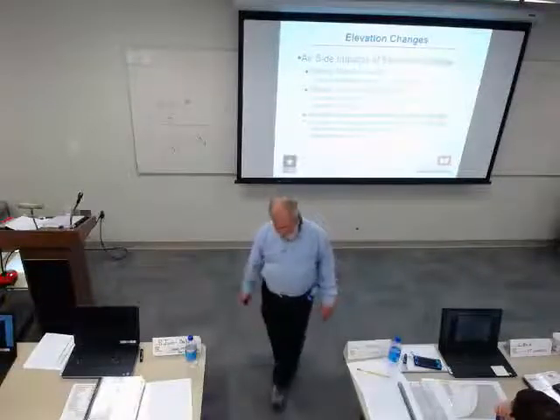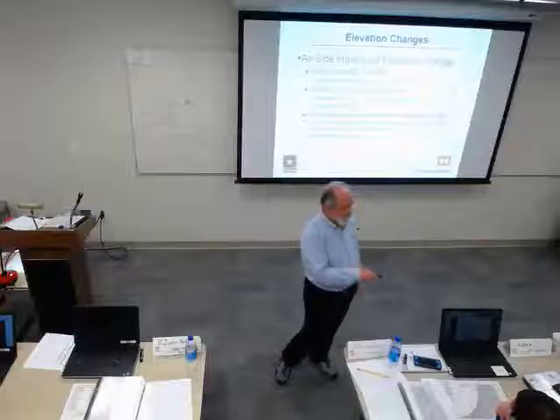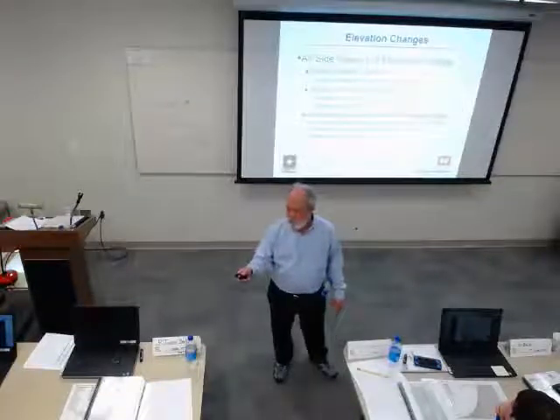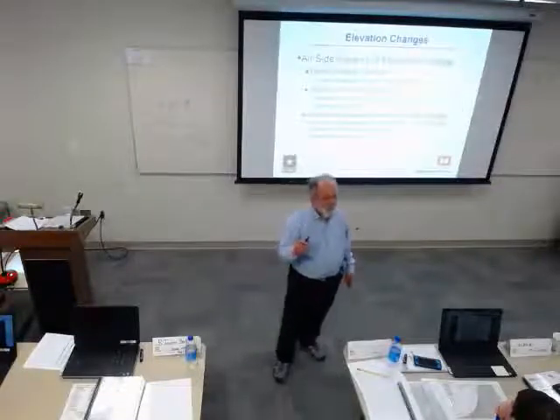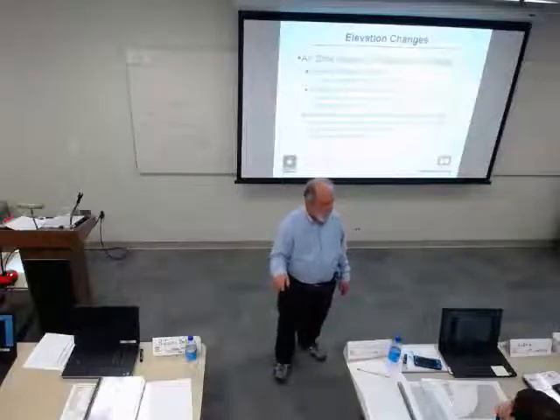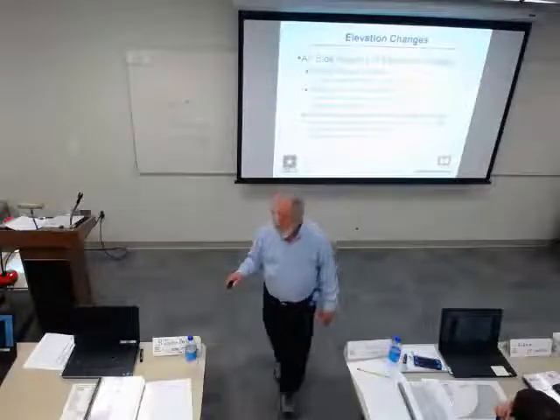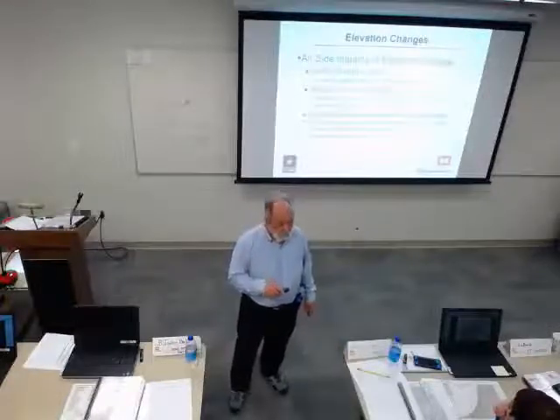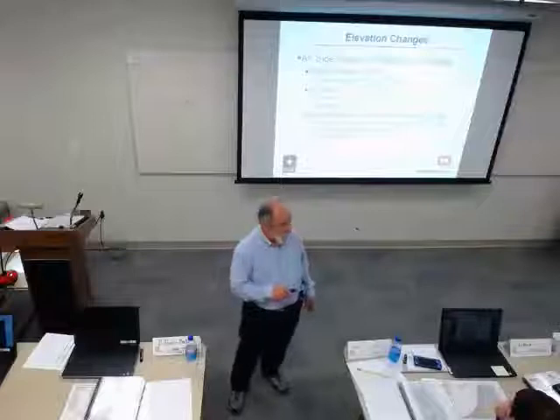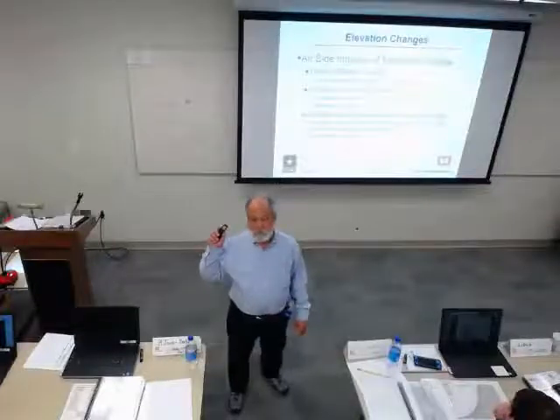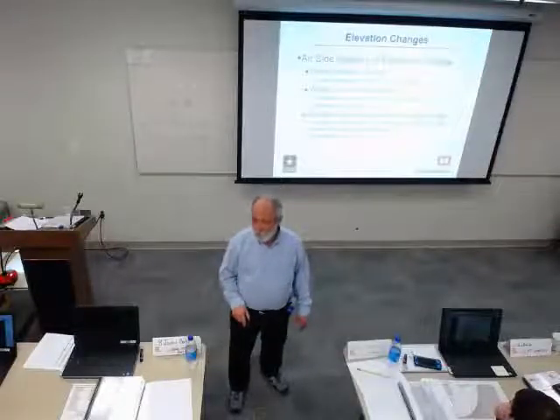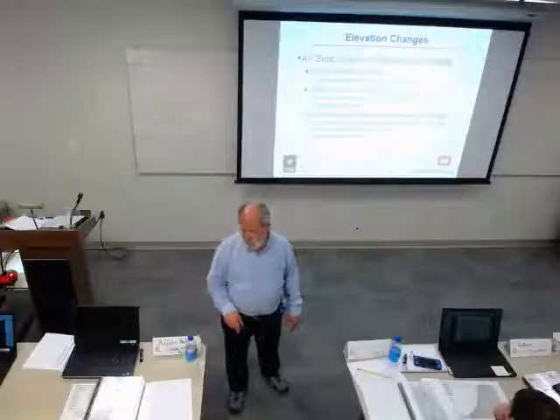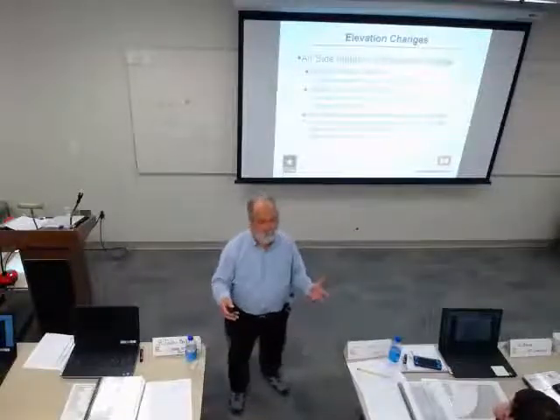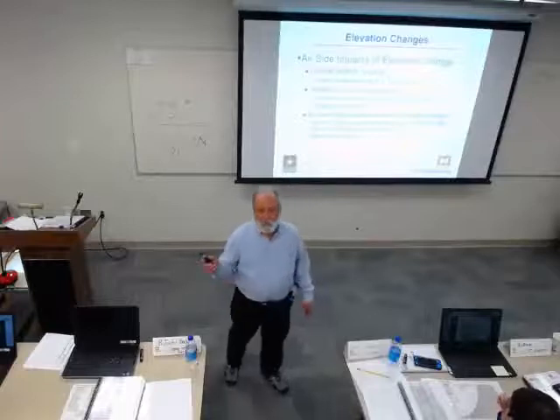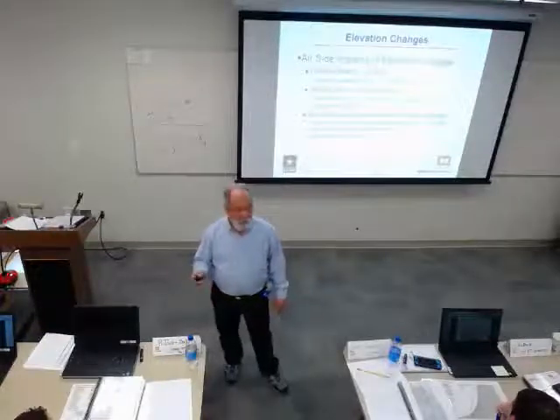He said, Vic, we're not going to, and I'll tell you why. All the stuff you've got is good. And I also found out why those things were. The thing that we still see today for relative humidity goes back to the days when we had card readers. If the humidity was too low, you had static electricity and the cards would stick together. If it was too high, they'd swell and you'd have trouble with the card reader again. So that was the limit there. And I said, that's great, we get rid of it. No, we can't. But anyway, my boss said we don't second guess the client.